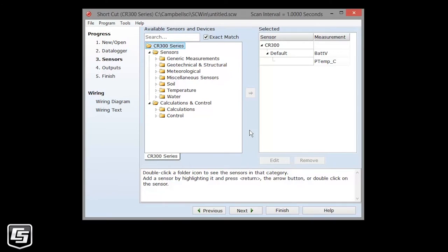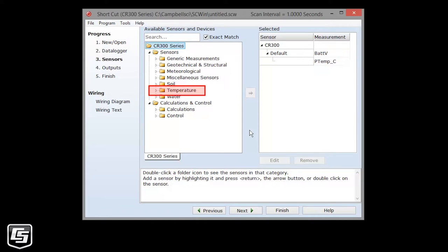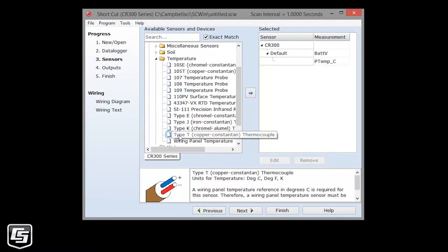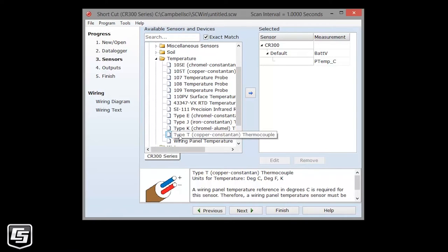We're using a Type-T thermocouple in our example today. One of these is shipped with every data logger. If you don't have one, you can use another sensor that you do have. Thermocouples require a reference temperature. For this tutorial, we'll be using the CR300's processing board's temperature, PTEMP, as our reference. Thermocouples are temperature sensors, so we'll select the temperature folder, and specifically it is a Type-T thermocouple, so I select that here. And add it to my sensor list by double-clicking or clicking this arrow.